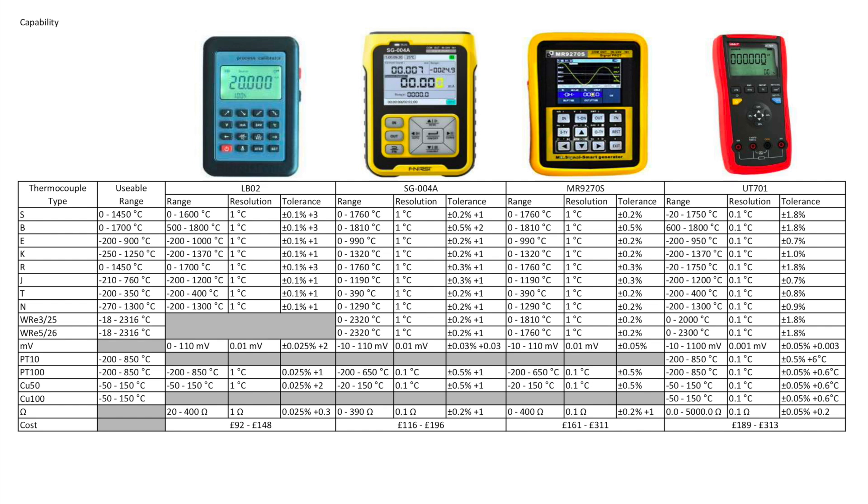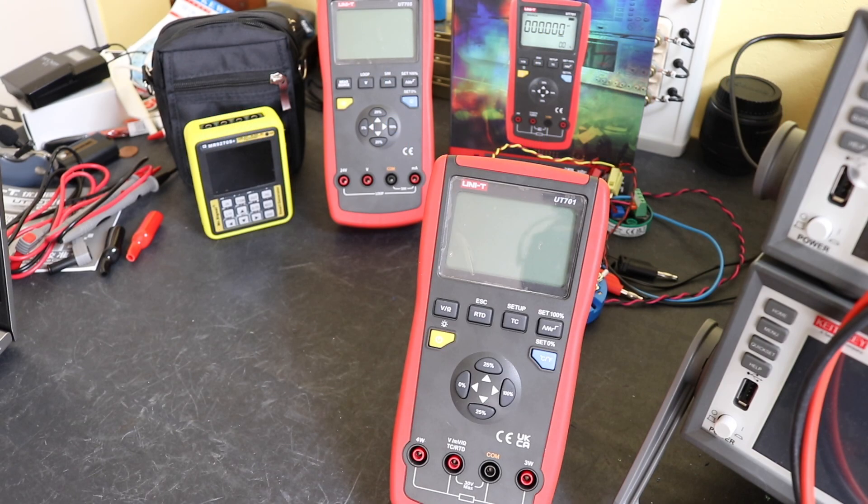Millivolt wise you can see it's pretty much the same kind of tolerance as our little process calibrator units. And again down at the RTDs you get the same kind of functionality. Still it's not quite as accurate as the LB02 with regards to resistance. But it should be better than our SG-004A and even our MR9270S on paper it should be better than those. And it does give me these other two RTDs that aren't included in the little process calibrator units, the PT10 and CU100. If you happen to deal with those kind of devices I don't deal with those so it's not that big an issue to me. But that's what its capabilities are in comparison to the little process calibrator units.